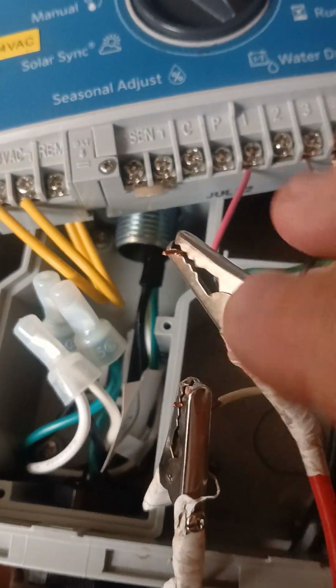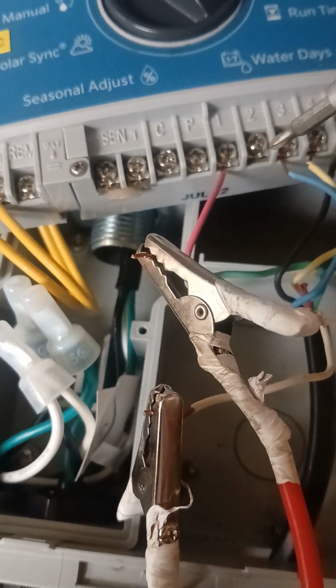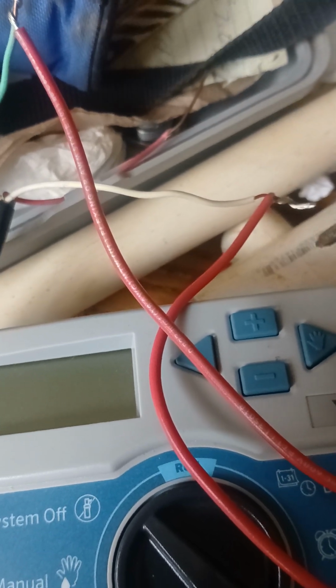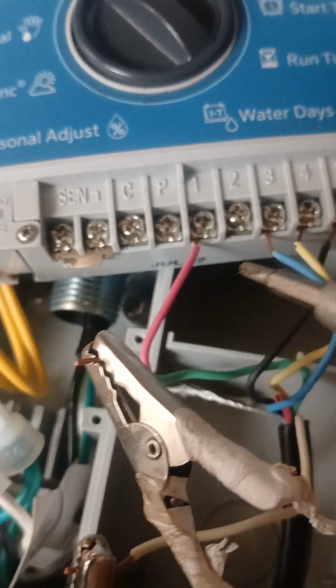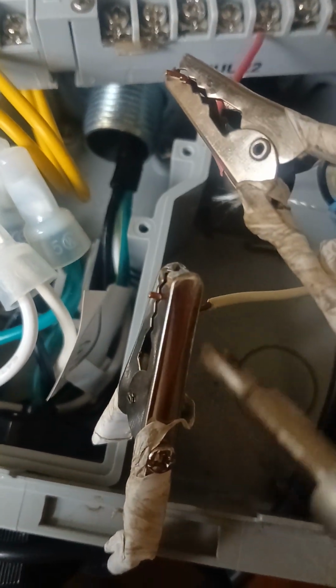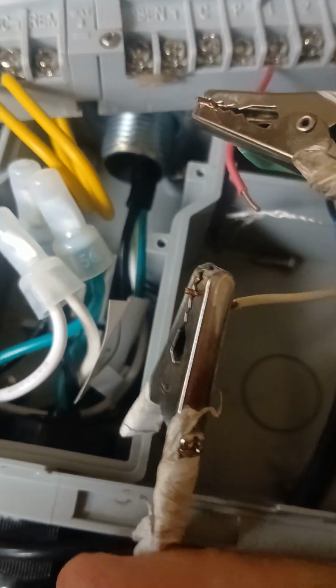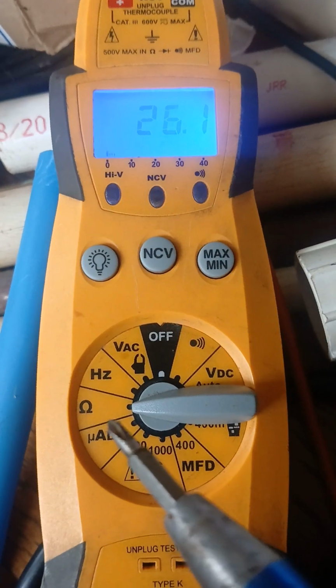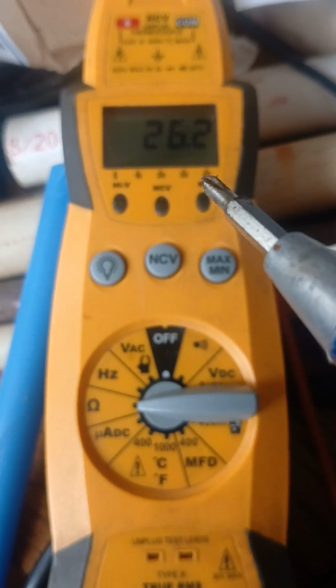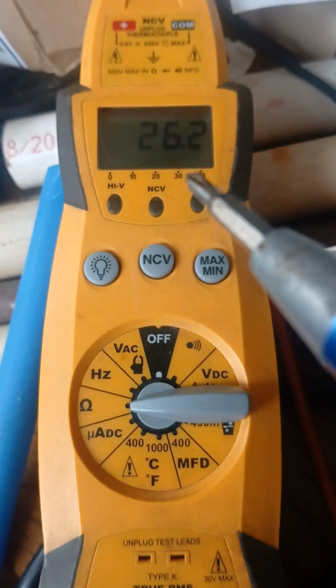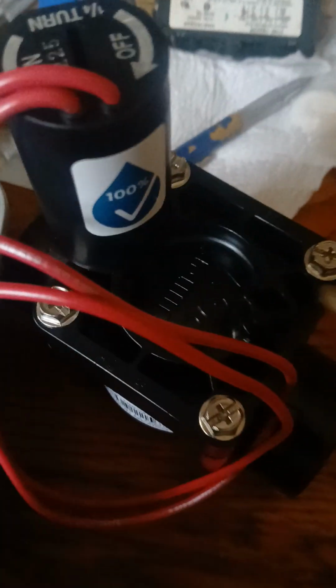Via the ohms. Again, we remove the common. We remove number 2, zone number 2, so that would be a hot wire. We simply put an alligator clip here and an alligator clip here, and then we tied the wires together. Now keep in mind, if these wires were out beside your house or somewhere, they would already be tied in, so you may not have to do this step. All you would have to do is remove this wire, remove this wire, and put either your probes or your alligator clips onto the wires you removed, which are the green and the white. Set your meter to ohms, and the reading is 26.2. So the range being 20 to 60, it would test good. Therefore, this valve may test good.